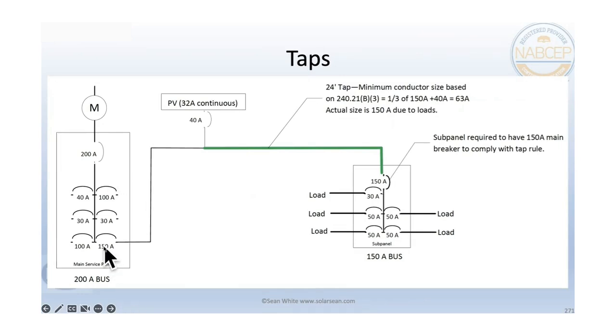So I take the feeder breaker, 150 amps, and then I add that to 125% of inverter current. So that equals 190, because 32 times 1.25 is 40. And so we've got 150 plus 40 is 190. And so what we have there is 190 amps times 1/3. 1/3 of 190 is 63 amps. So if this conductor is at least 63 amps and it's going less than 25 feet, we're good. So we could put the breaker over here. If it went 26 feet, then we would need to put overcurrent protection closer over to here.